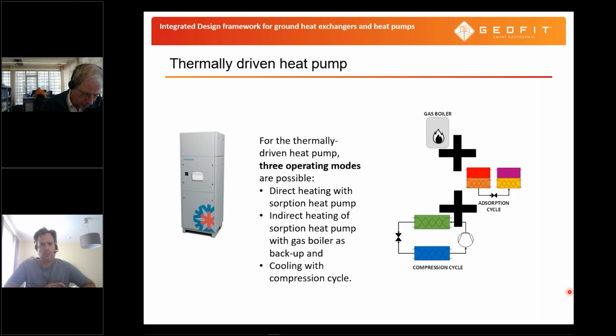So we can use such systems with a smaller geothermal field, which is an advantage in terms of invest cost. Also, the requirements on the electric infrastructure are less strict than for electrically driven heat pumps. For instance, when we consider old settlements in rural areas, they have a limited connection power, and sometimes you cannot drive your compression heat pump with those boundary conditions. Further, for such a thermally driven heat pump, it is possible to use an existing gas boiler to drive the system, as it says, thermally driven.